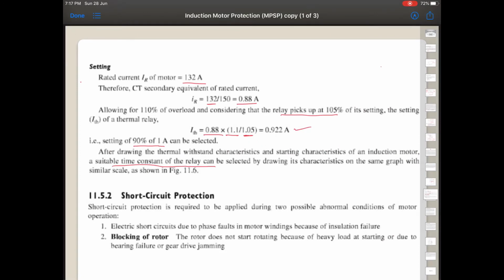So this protection is required during two possible abnormal conditions of the motor. First is electric short circuit due to phase faults. This happens because of insulation failure. If there is a large current, a large amount of heat is produced in the induction motor, then the insulation may break down, and because of the breakdown of insulation, the two conductors may get short circuited. So we are referring to it as electric short circuit.